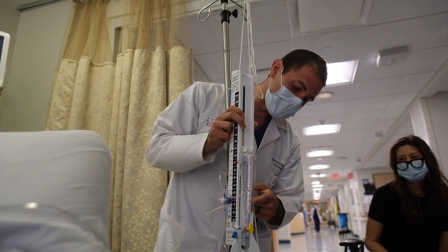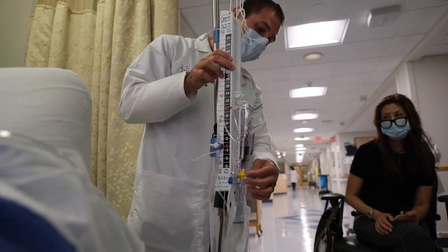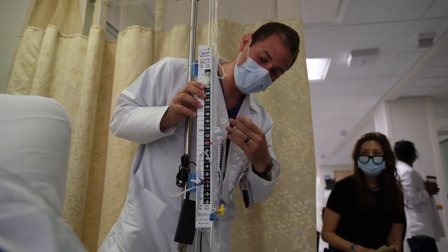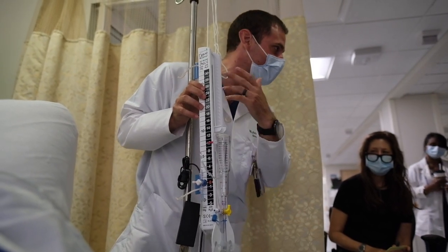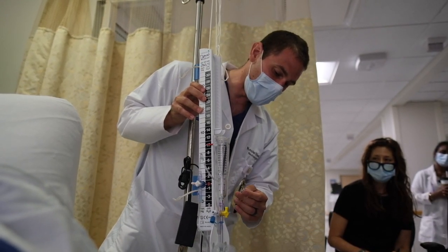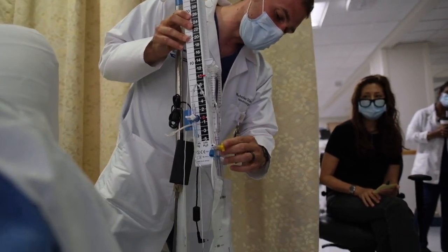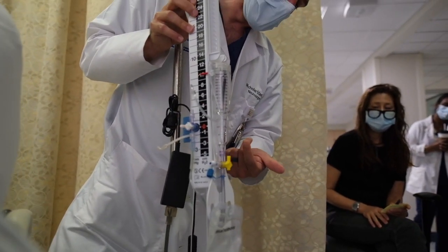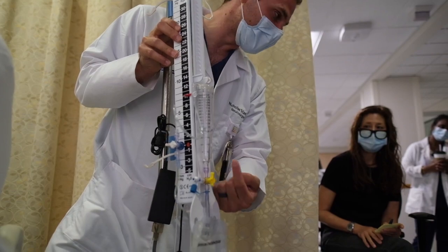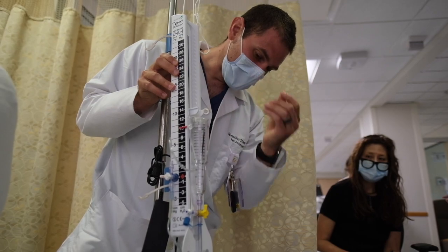So we come to our collection chamber here. As you can see, it can hold up to 75, 80 cc's. We hope nobody drains that in an hour. When the drain is in its open position, anytime there's a higher pressure, the CSF is going to drain into the chamber here. The next part you're going to see here is the stopcock. Again, this is a three-way stopcock as well. In order for it to collect, you want the off part of the tab in the up position so it collects.